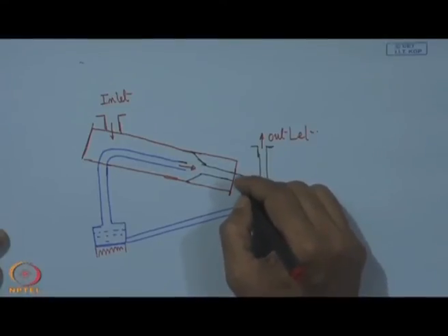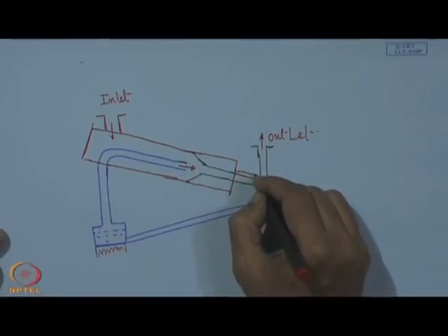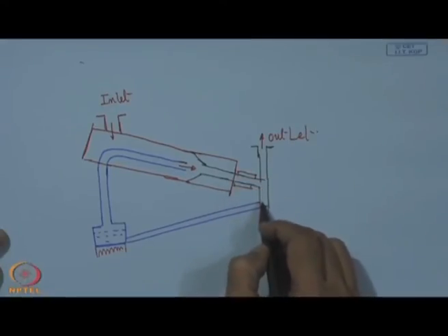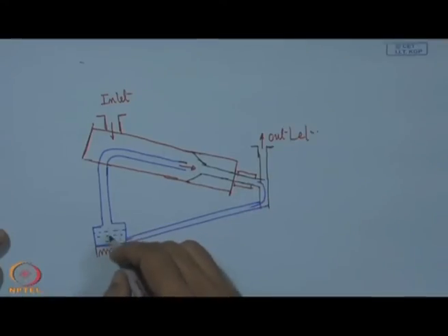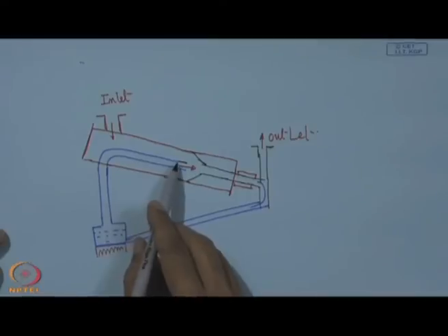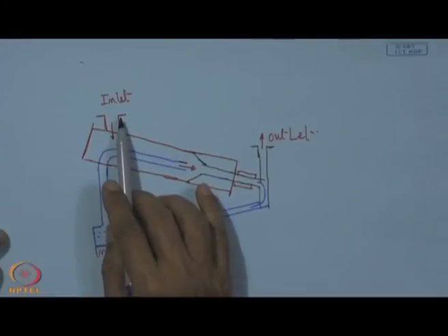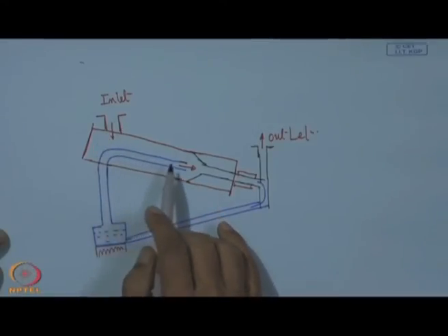Here we have water cooling in this zone. With this water cooling, we can recycle this oil vapor, which will be flown back through this line and recycled. So, it is actually the creation of the oil vapor, and this oil vapor entrains the gas molecules from the chamber, and then they will be dragged.